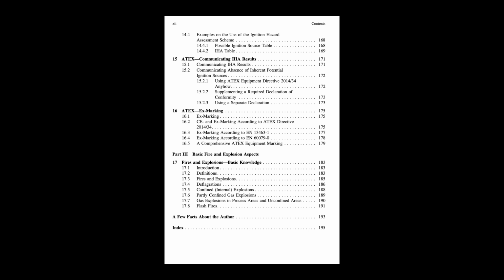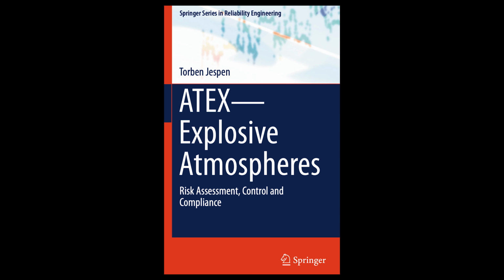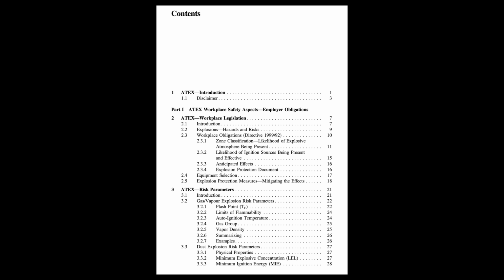This allows the pressure, the flame front, and any unburnt material to escape to a safe location, usually outdoors. So it limits the pressure buildup inside the equipment itself. Precisely. It gives the explosion a controlled escape route, preventing the equipment from rupturing catastrophically. But you mentioned venting it safely. What about the fireball and pressure wave coming out of the vent? That's a huge consideration. The guide stresses this. You absolutely have to account for the effects outside the vent, the flame jet, the pressure wave. You need a clear, safe discharge area. And you have to consider any potentially toxic materials being released. Right, can't just vent toxic dust anywhere.